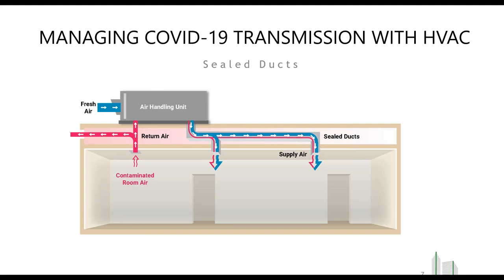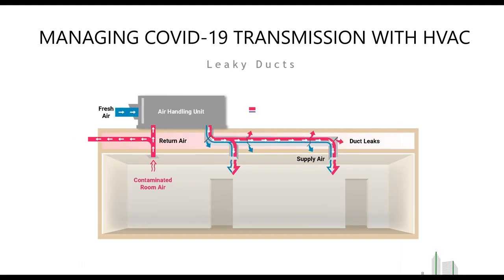And why that's so important is that you're actually diluting all of that contaminated room air. I've been on lots of calls and webinars from different groups. There was one at the UC Davis lab a few weeks ago where they were talking about how important it was to reduce CO2 in the rooms, and if you can't bring in enough outside air, how you need to even open the windows. But the whole time I was thinking, well, if your ducts aren't sealed properly, which is what I show in this document, then you're going to have a lot of problems just meeting what you're supposed to do by design, let alone what's going to happen when you're trying to increase that amount of fresh air that's coming in.